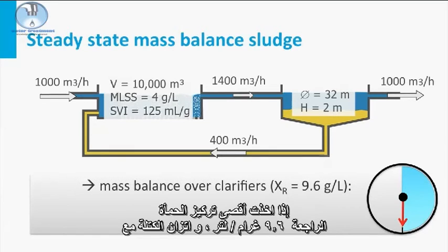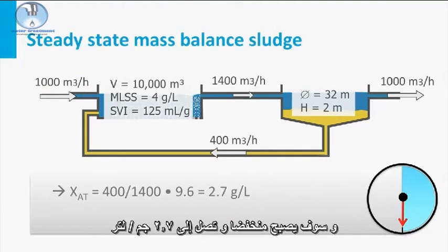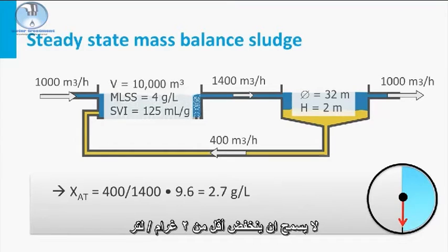If you take the maximum return sludge concentration of 9.6 grams per liter and the mass balance with the storm water flow of 1000 cubic meters per hour, you can calculate that the new concentration in your aeration tank will become as low as 2.7 grams per liter. This is fine, since one of the rules of thumb is that the concentration in the aeration tank is not allowed to drop below 2 grams per liter.